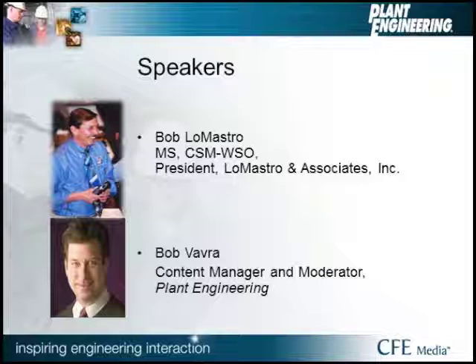Yeah. Good. Bob, I see a question here that I think we should address. It says, I have an Ideal Voltcom meter or a Wiggy, and how do I determine the category of the meter? And the answer to that is, if it's not labeled on that meter, then it's not currently up to standards and should not be used in the workplace. Very good. That's an important one, and I think the whole point of 70E and these standards is to bring things up to current specifications, and that's a great point to make.